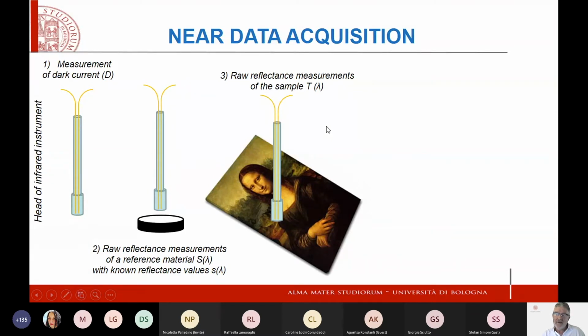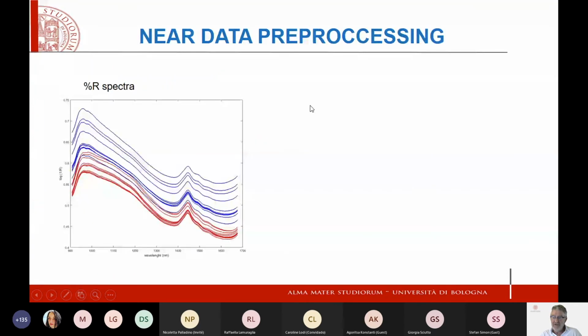How are the data acquired? The technique foresees the measurement of a dark current. Here you can see the head of the instrument, and then you need to collect the raw reference measurement of a standard sample with known reflectance values, and then you can go directly on your object and collect, without touching the object, in a non-invasive way, the near-infrared spectrum.